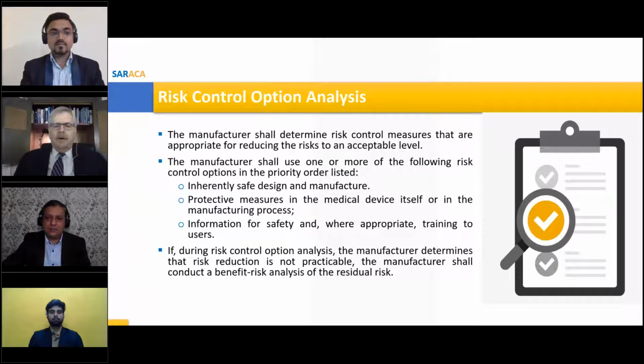So from a risk control option analysis, the manufacturer shall determine the risk control measures appropriate for reducing the risk to an acceptable level. You can do this by or as part of 3 levels of risk control options. The first one is inherently safe design and manufacture. This particular one is now related to ISO 13485 in that 13485 needs you to do the risk assessment before you do your design inputs, meaning you have to do your risk analysis at the same time you're designing your product and ensure that you have an inherently safe design.